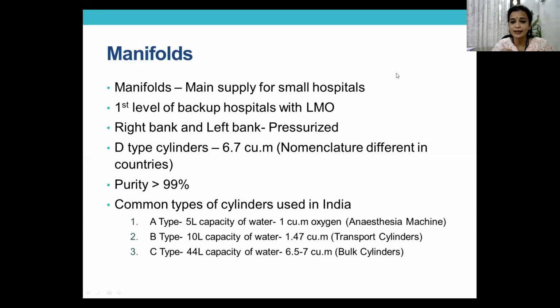Now the nomenclature again differs from country to country. In the UK, you have this D, E, F and J. In India, we have this A, B, C and D. So what is connected to this manifold is actually the D-type cylinders in Indian nomenclature. These D-type cylinders hold about 6.7 cubic meters. And the purity is very good because the oxygen is filled directly by filling stations. So it is over 99% purity.